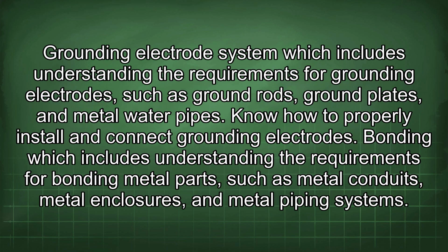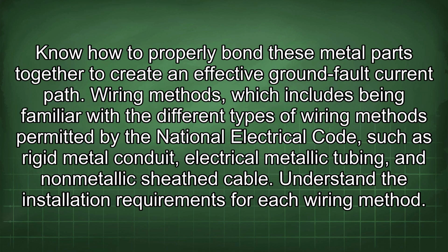Grounding electrode system, which includes understanding the requirements for grounding electrodes such as ground rods, ground plates, and metal water pipes. Know how to properly install and connect grounding electrodes. Bonding, which includes understanding the requirements for bonding metal parts such as metal conduits, metal enclosures, and metal piping systems. Know how to properly bond these metal parts together to create an effective ground fault current path.